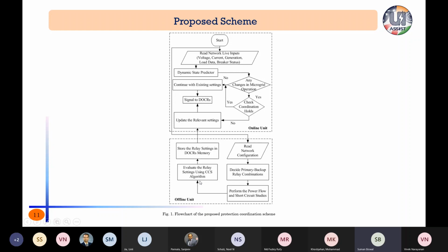Then, based on the short circuit studies, the relay settings will be calculated and we will store them in the relay. In a numerical relay, we have the provision for storing setting groups. I have seen 6 setting groups for the SEL-451 relay, so that can cover at least 24 topologies: 6 setting groups, and each setting group can take care of 4 subsettings. The online part will detect any change in the network, and if the coordination conditions all hold, it will maintain the settings. Otherwise, the settings need to be updated. So this is our proposed idea of implementing the coordination scheme.